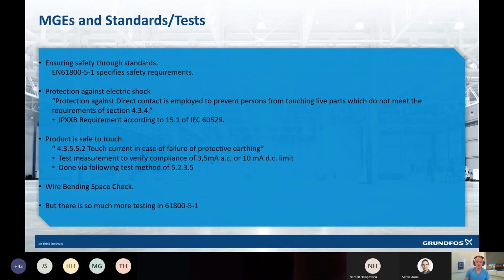It also needs to fulfill everything else the standards don't cover, as mentioned earlier. A good example is foreseeable misuse. For example, if you say you cannot have this cover off with the power on, but you know service people will take it off because they might need to do a reading or measurement, you need to cover this foreseeable misuse through risk mitigation and a risk assessment.